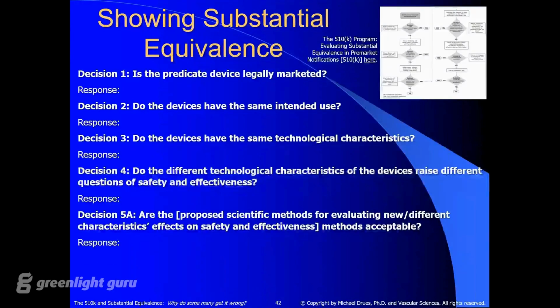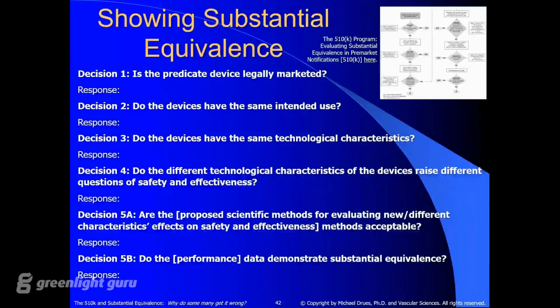Then finally, we get to decision 5, which is in two parts. Are the proposed scientific methods for evaluating new or different characteristics of safety and effectiveness acceptable? It's an interesting kind of phrase to that question. Acceptable to whom? I guess in this particular case, acceptable to FDA, but remember, it's our job to convince them of what's acceptable. And finally, does the performance data demonstrate substantial equivalence? And this is where we do oftentimes a benchtop head-to-head comparison. We do a test on our device and the same test on the predicate device, and we compare the data head-to-head, so to speak. We have to address all of these questions in order to get through the flow chart.